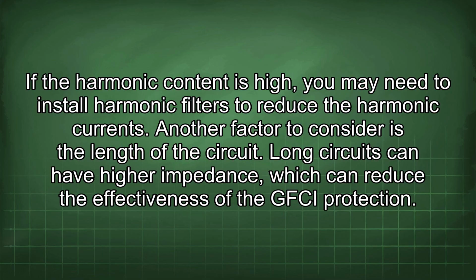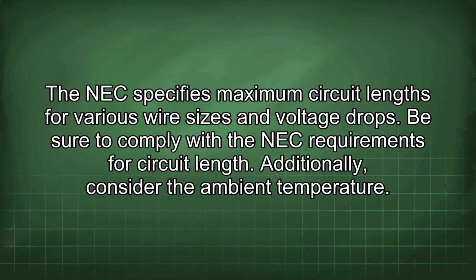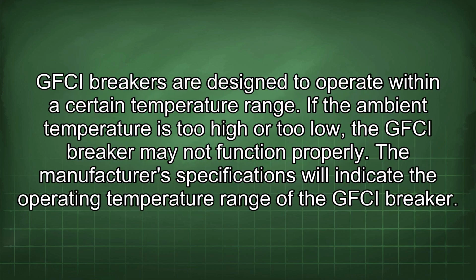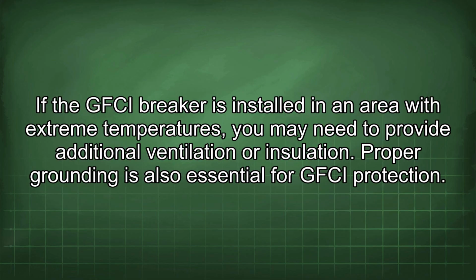Another factor to consider is the length of the circuit. Long circuits can have higher impedance, which can reduce the effectiveness of the GFCI protection. The NEC specifies maximum circuit lengths for various wire sizes and voltage drops. Be sure to comply with the NEC requirements for circuit length. Additionally, consider the ambient temperature. GFCI breakers are designed to operate within a certain temperature range. If the ambient temperature is too high or too low, the GFCI breaker may not function properly. The manufacturer's specifications will indicate the operating temperature range of the GFCI breaker. If the GFCI breaker is installed in an area with extreme temperatures, you may need to provide additional ventilation or insulation.